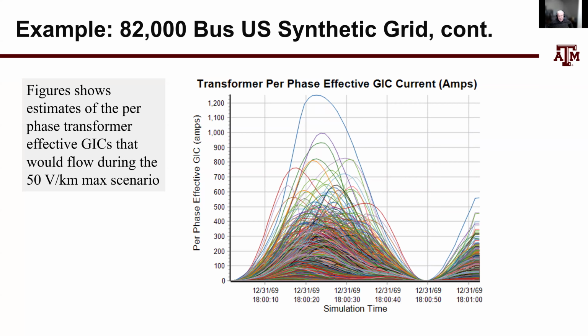To put this in context, the NERC TPL-007 standard for GMD says if a value goes above 75 amps per phase in a transformer, that's the threshold. You can see here that we are getting many transformers with values multiple times that, and a couple of transformers have values that are at 10 times that value. What that would do to the transformers, we're not sure. So when people talk about testing transformers with GICs, certainly you want to test at the 10, 20, 30, 40, 50 amp values, but it would also be good to know what happens if they get 2, 3, 4, 500 amps of GIC in them.